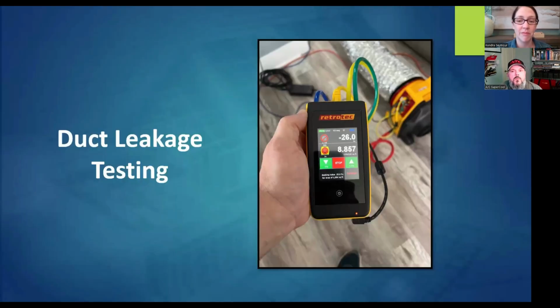So once we get everything designed and installed, duct leakage is a critical step. This is one of the biggest detriments that causes major deficiencies, not specifically on the AC side of the equation. It wreaks havoc on the house itself, and people don't realize this, but it really does. So duct tightness is critical to the performance of the system and the home, and I stress home there.